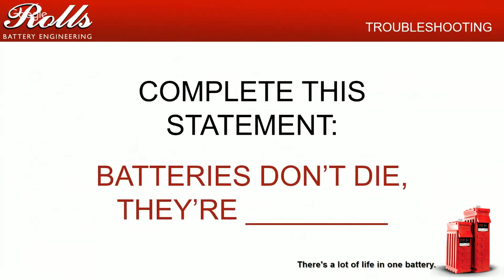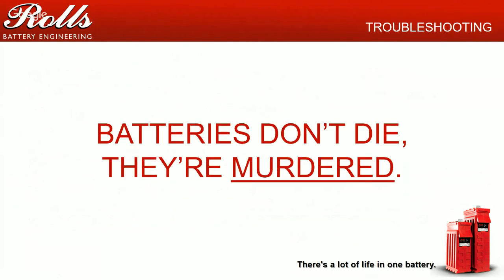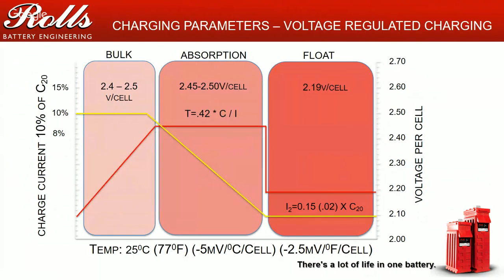This is a very important thing to understand. Most customers don't know it, but batteries just don't die. In most cases, they're murdered by the customers, by the end users. What I mean by this is that most often customers or installers alike aren't properly charging the batteries. It's very important to understand the entire charge process.